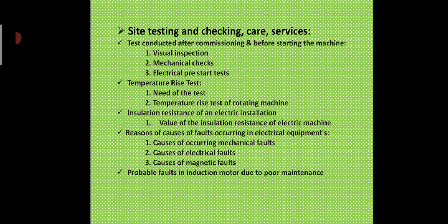In electrical pre-start tests, the tests are performed before starting the machines. First is measurement of resistance of the winding, measurement of the insulation resistance of the winding, high voltage test, trial start, no load test, on load test, test on cooling system, test on lubricating system, and tests like starting and running characteristics, reversing, braking, etc. Special tests like vibrations, noise, and oscillography for record of starting current.